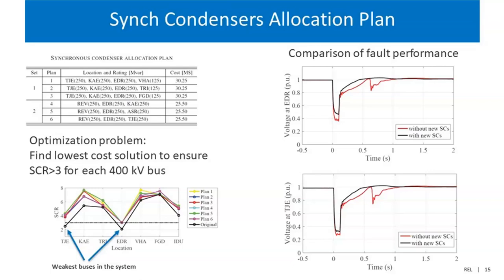there are two buses in the system that are very weak. But when we run through these deployment plans, you can see that, of course at a different cost, it's possible to keep every single bus meeting that short-circuit ratio criterion. In addition, the transient performance of the system improves too. There are a couple of sample buses here, and the black one is the system response with synchronous condensers, so you can see there is less voltage drop and also a better recovery process.